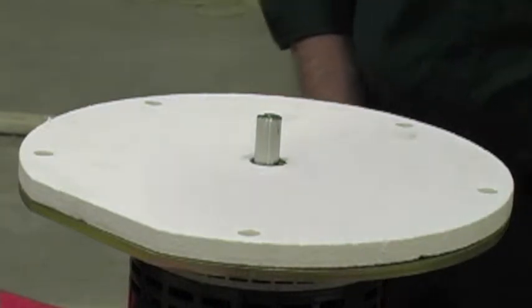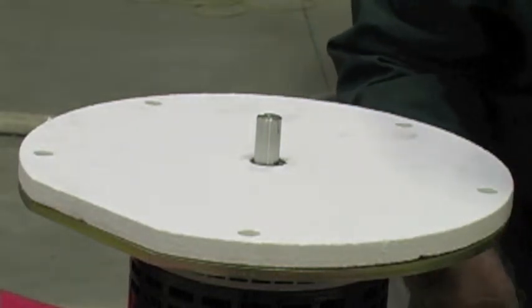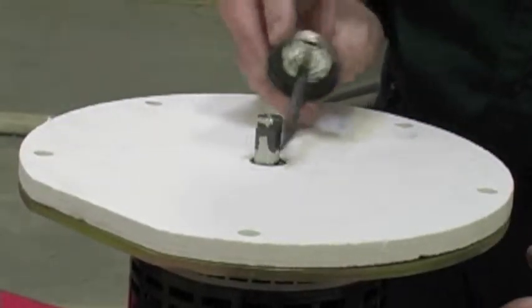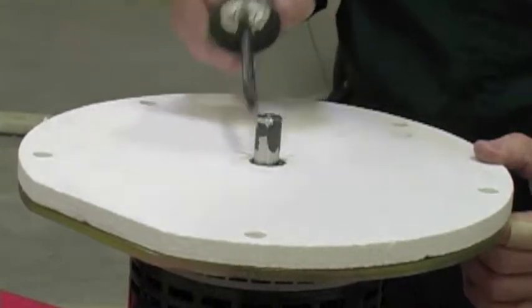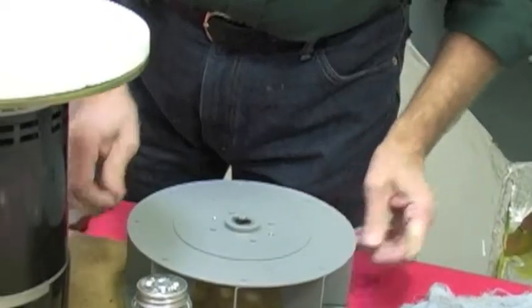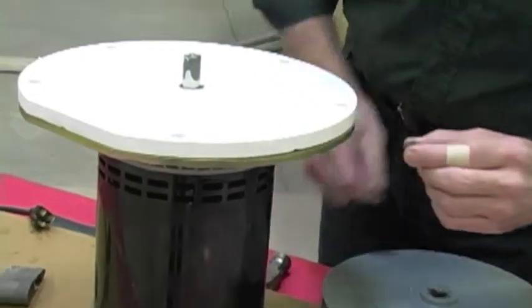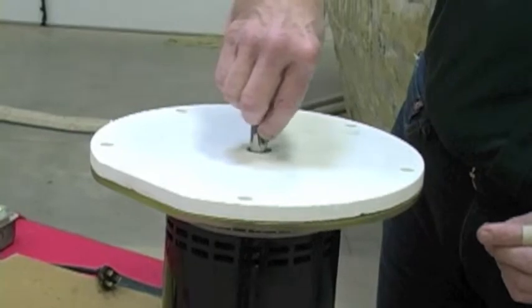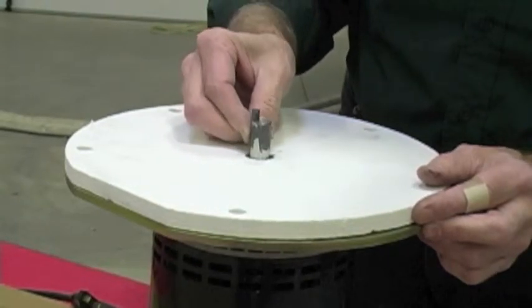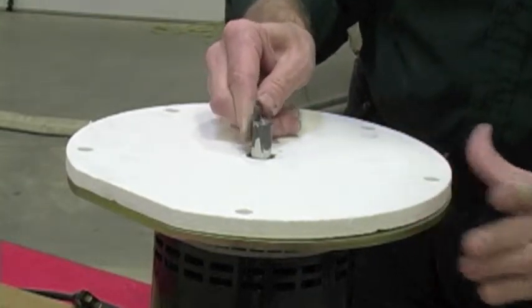The next item is to take some high temperature anti-seize compound and brush a little bit on the shaft. You want to get it around the shaft as best you can and in the keyway — this will prevent the blower wheel from sticking in the future. The final step before you put the wheel on is the key that goes in on the shaft to prevent the blower wheel from sliding. Put the key in position, but leave the key proud of the face of the shaft — you do that for alignment purposes.